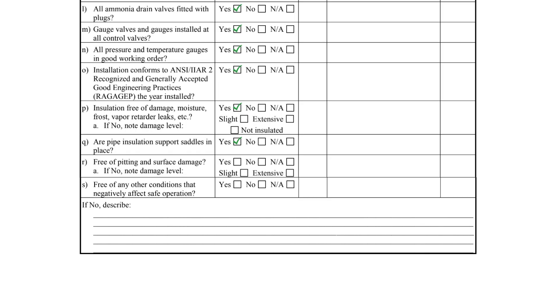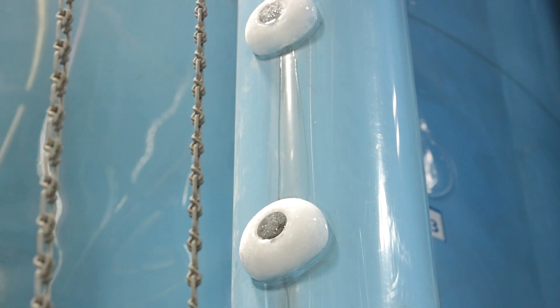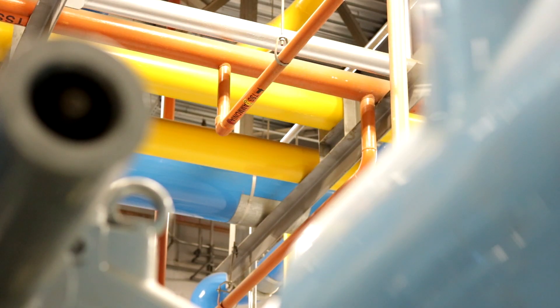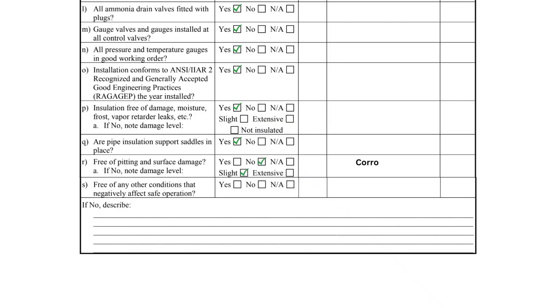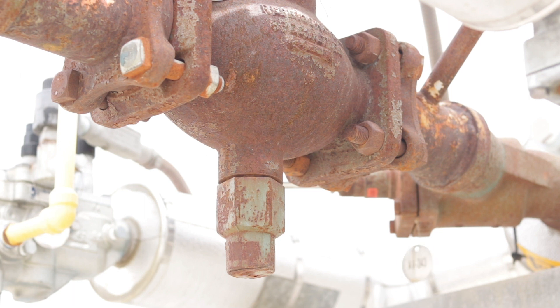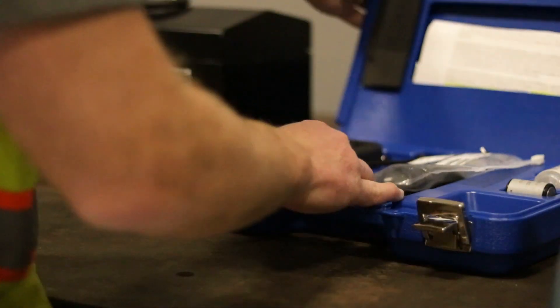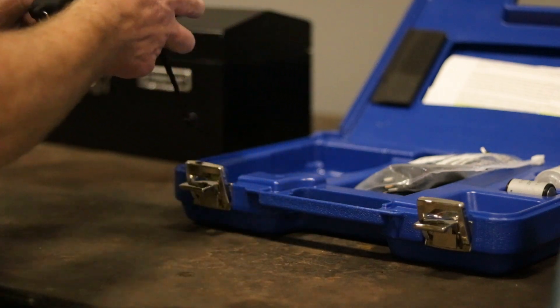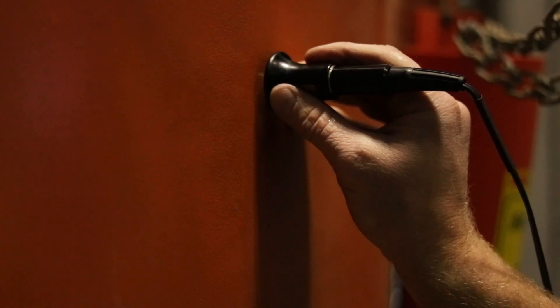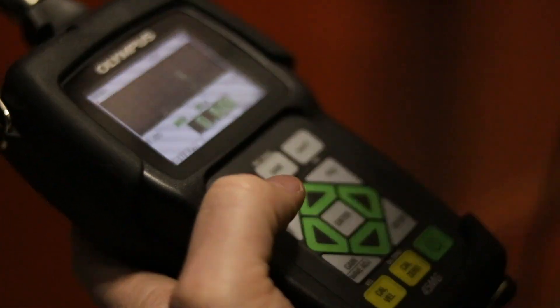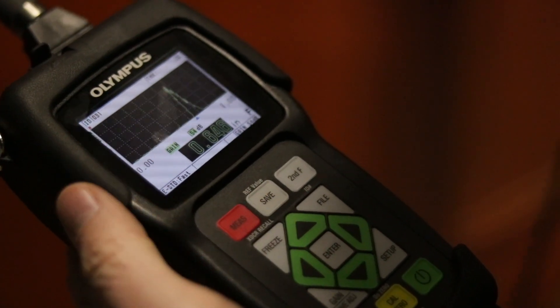The inspection checklist concludes with items R and S. Item R requires the entire surface of the piping to be inspected and any surface corrosion or pitting must be recorded as a deficiency. If a deficiency is noted, an additional checkmark is required to indicate if the damage is slight or extensive. This suction isolation valve has slight external corrosion. While not specifically listed in the checklist, ultrasonic thickness testing can be used to gauge the amount of material lost due to corrosion. Thickness readings can be used to determine if the pipe is fit for service and the remaining useful life.